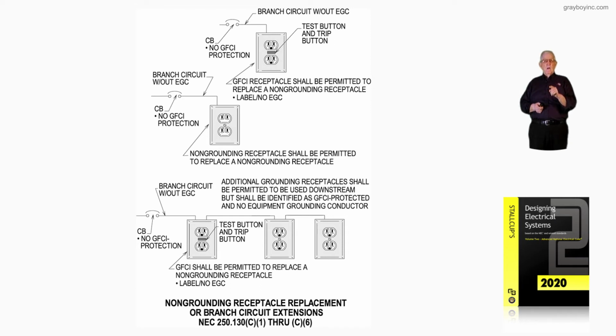Or we could use the next set of receptacles and the branch circuit without an equipment ground, no ground fault protection. And if we didn't have an equipment ground, then notice we could have a test button and trip button type GFCI, and it would be permitted to replace a non-grounding type receptacle without an equipment ground. And then the downstream receptacles could be of the non-grounding type with a label, "no equipment ground," identification to show one is not present.